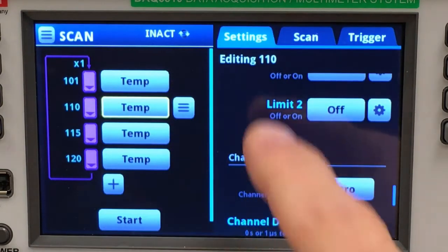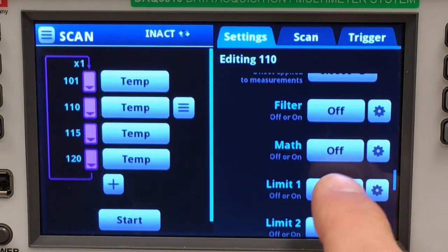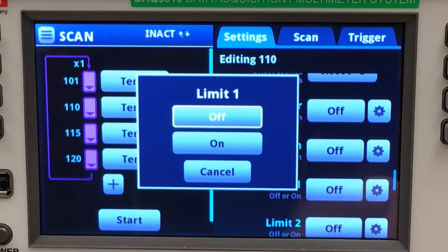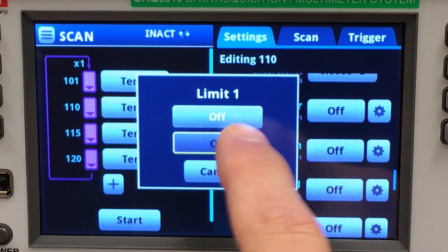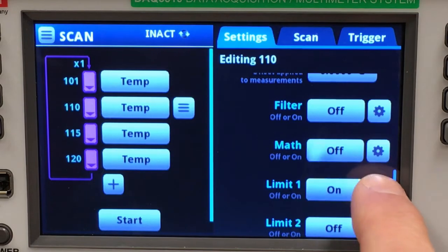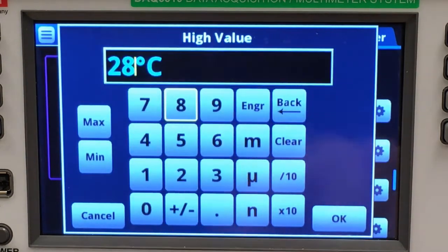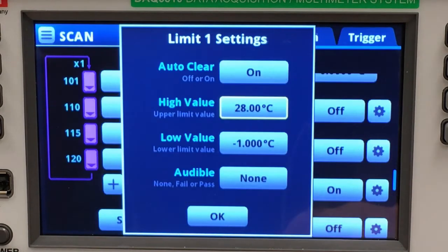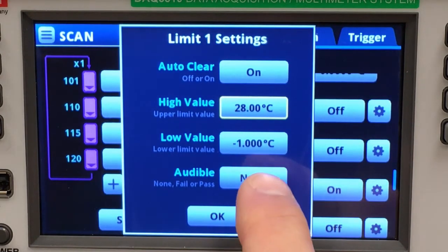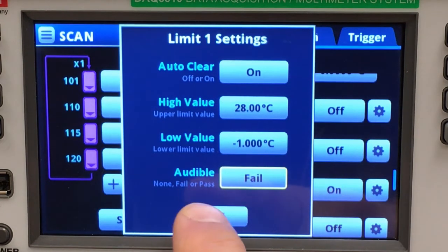Channel 110 is monitoring a microprocessor and it has a tendency to get hot. Let's provide ourselves a notification if something goes wrong and we hit that condition, so I will establish a limit. I will set a high value of 28 degrees C, and if my back is turned I want to hear if the limit has been exceeded. I accept.